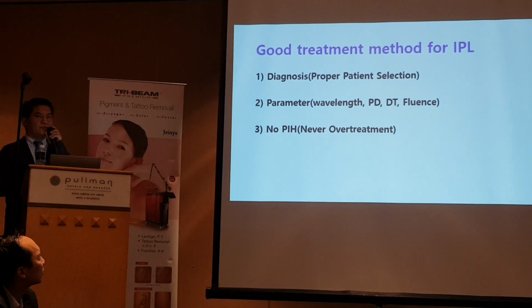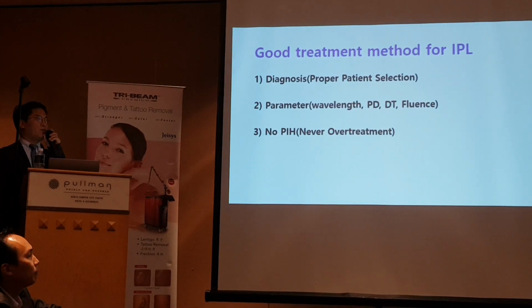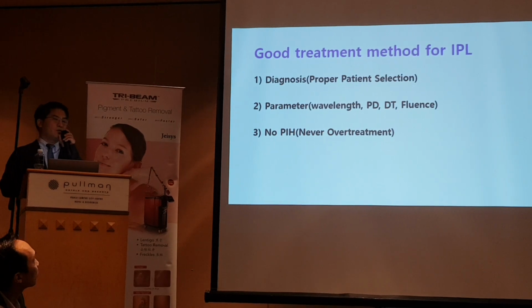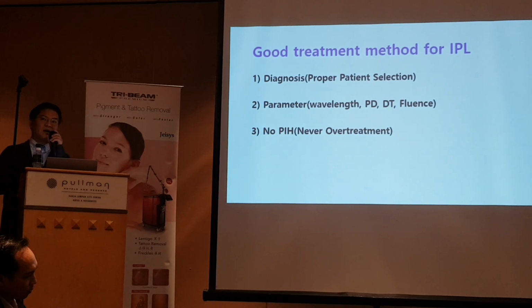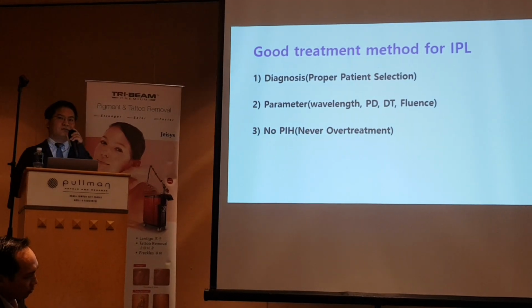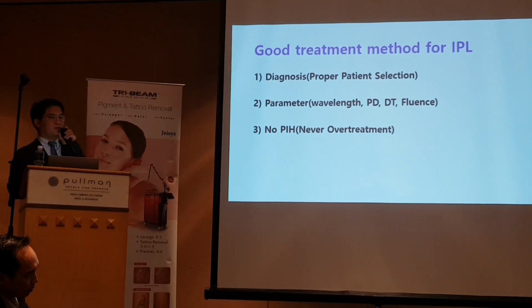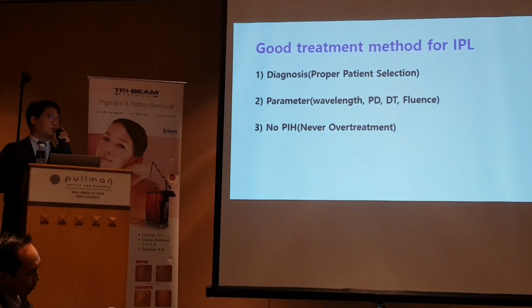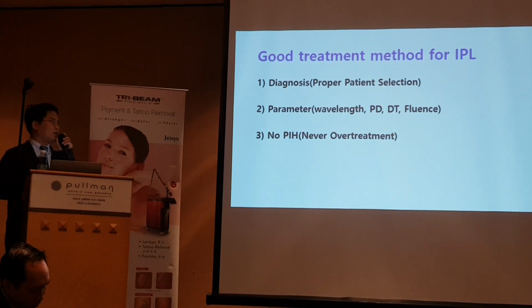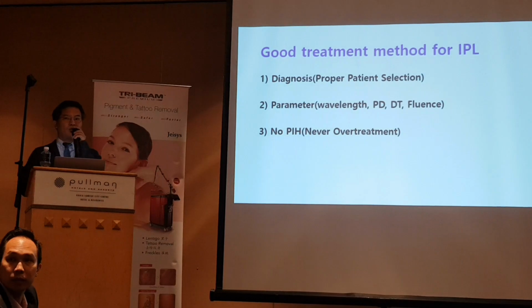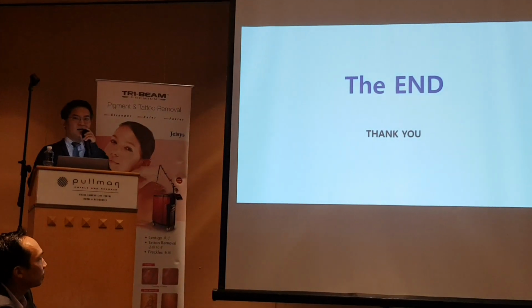Good treatment method for IPL. First is proper patient selection for good diagnosis. Usually epidermal pigment lesion, freckle, lentigo. Second, parameters: wavelength, pulse duration, delay time, and fluence. Third, never over treatment. The end. Thank you.